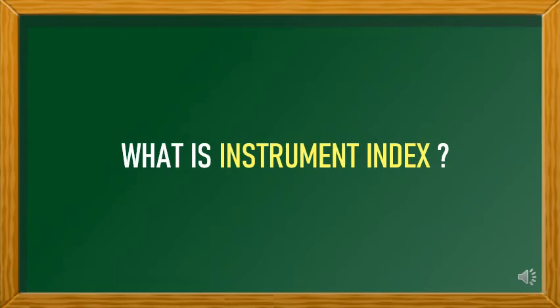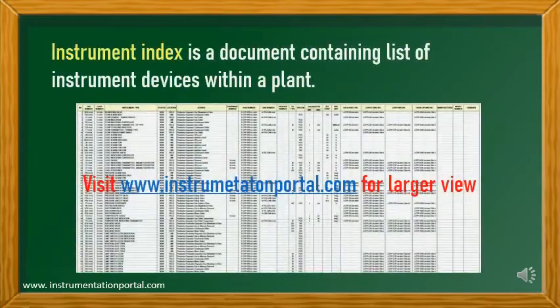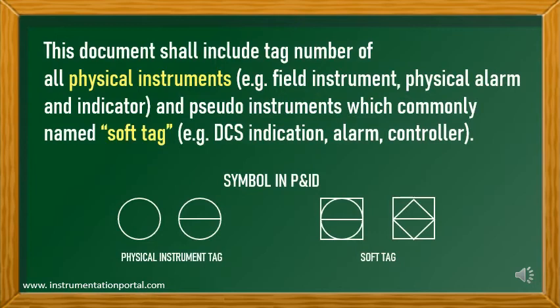What is instrument index? Instrument index is a document containing a list of instrument devices within a plant. This document shall include tag numbers of all physical instruments, for example field instruments, physical alarms, and indicators, and pseudo-instruments which are commonly named soft tags, for example DCS indication, alarm, and controller.